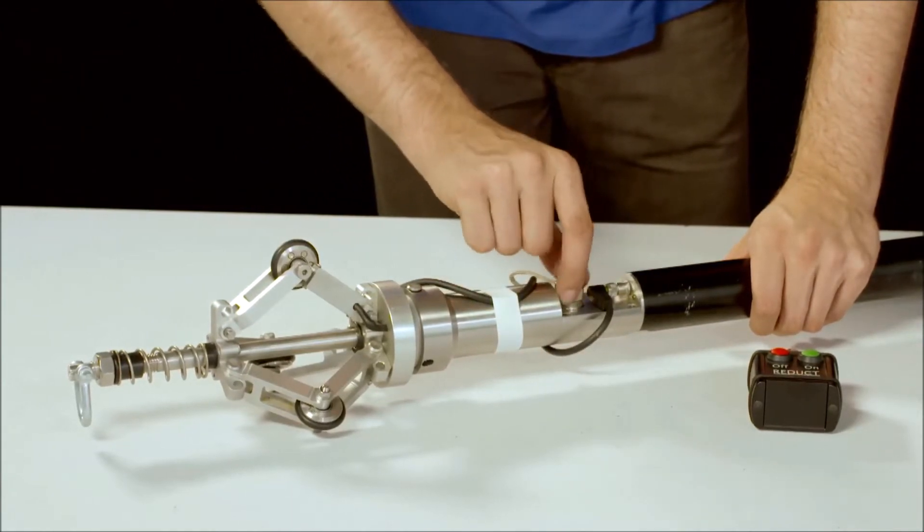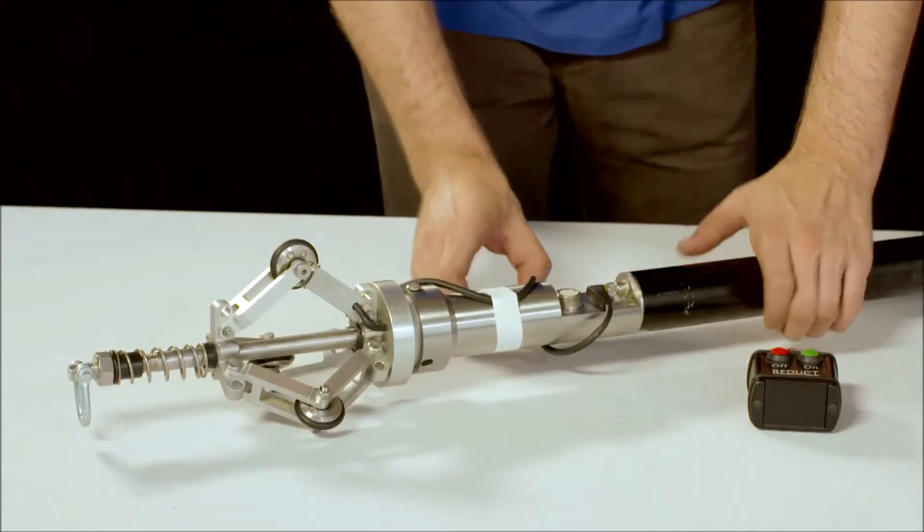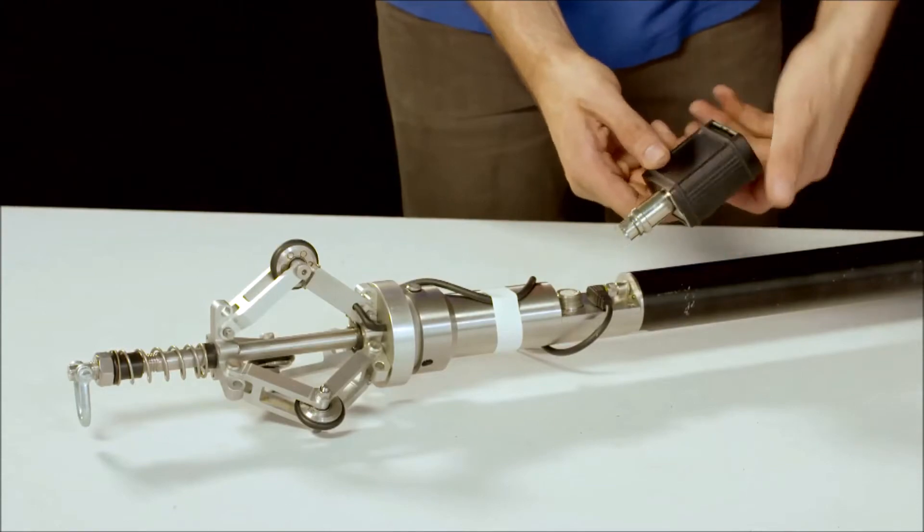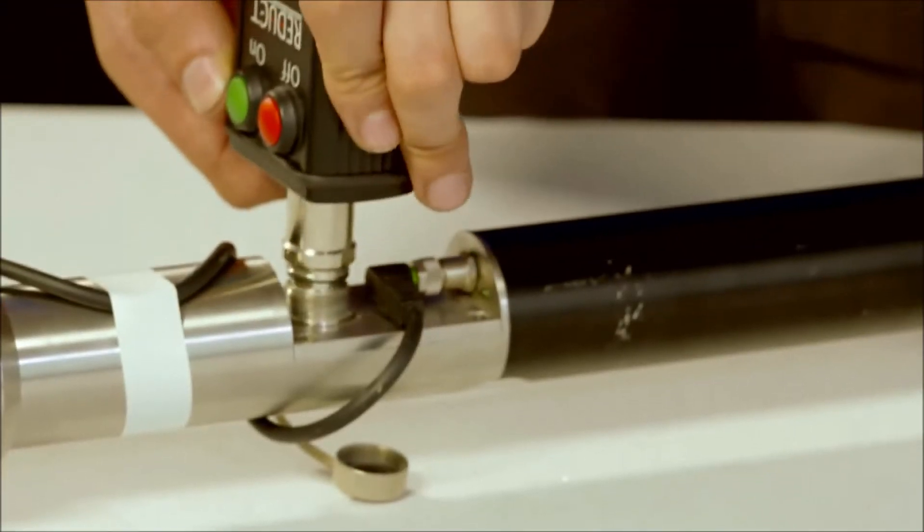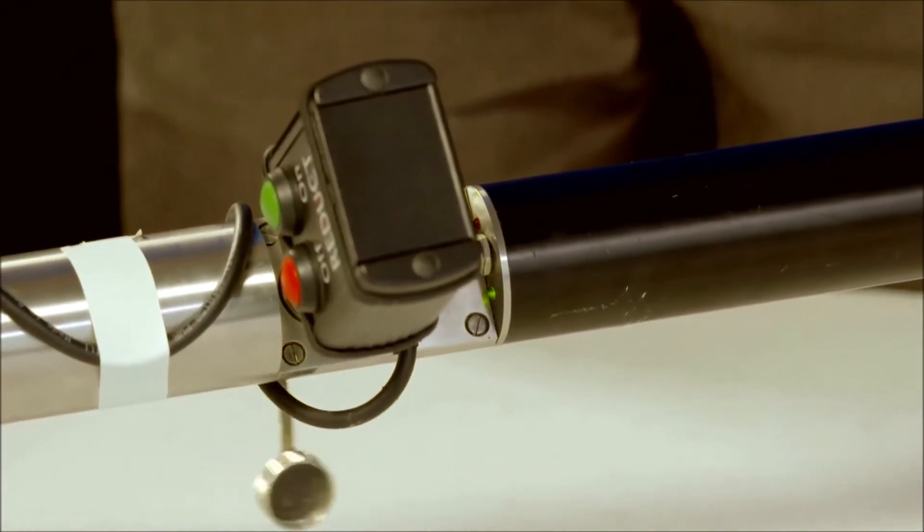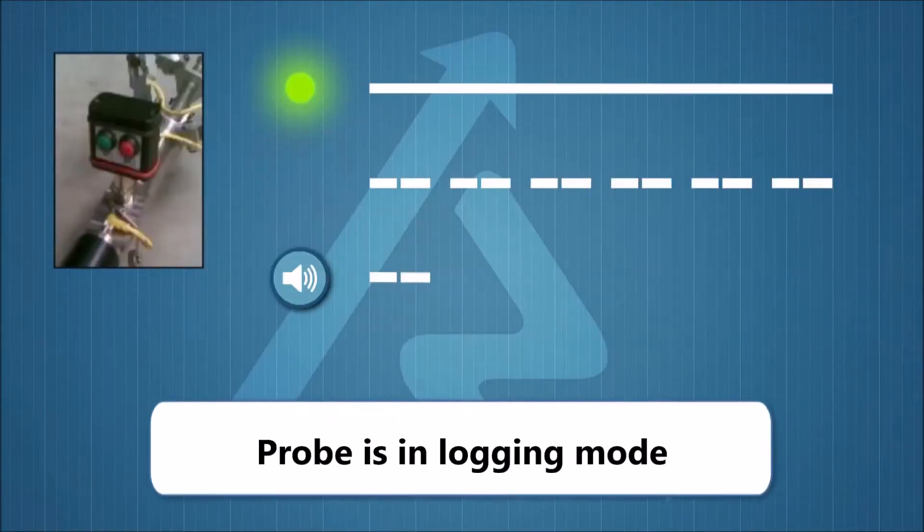To switch the probe on, remove the protective cap manually. Insert the control unit and press the on button. If, after switching the probe on, you hear two beeps, the green LED is on continuously, and the red LED flashes twice intermittently, the probe is in logging mode and ready to map.